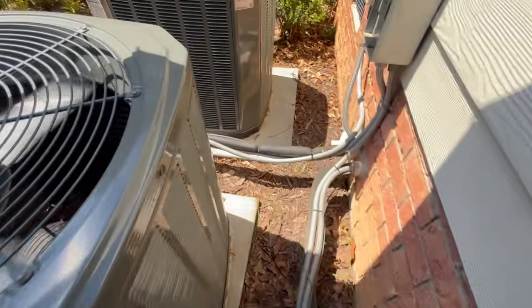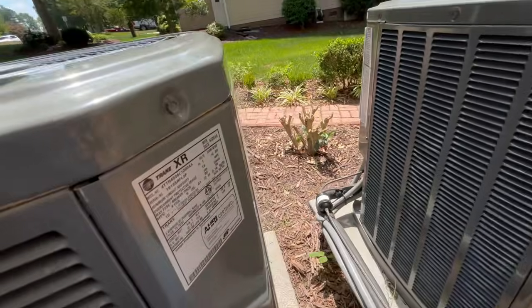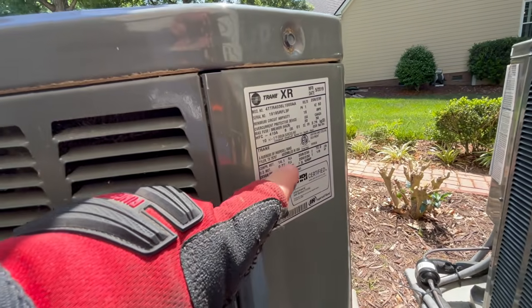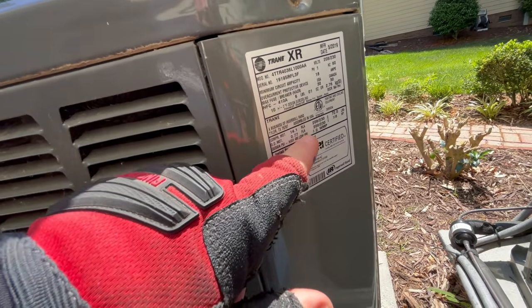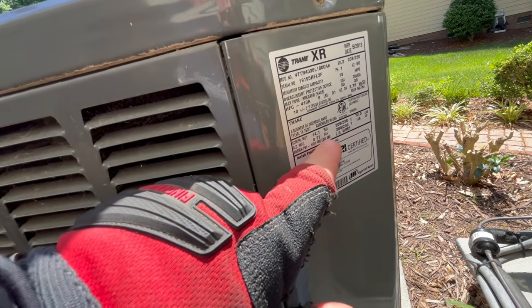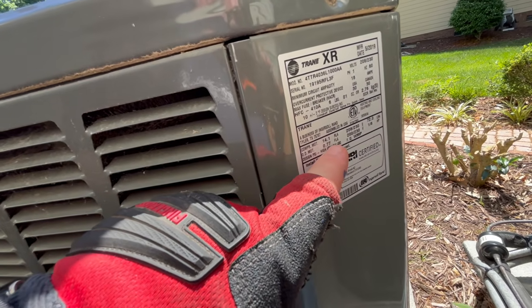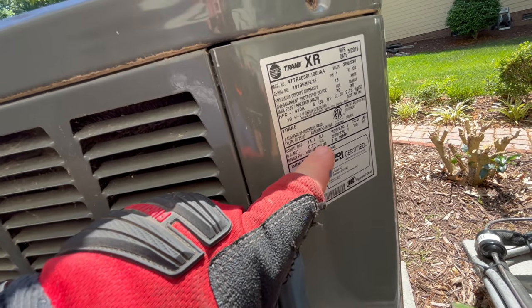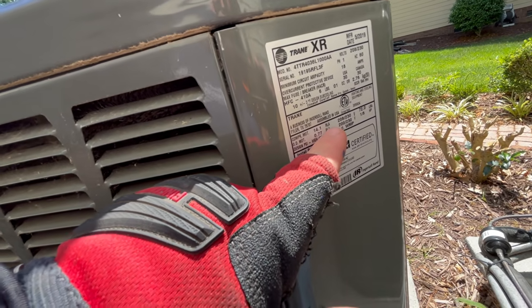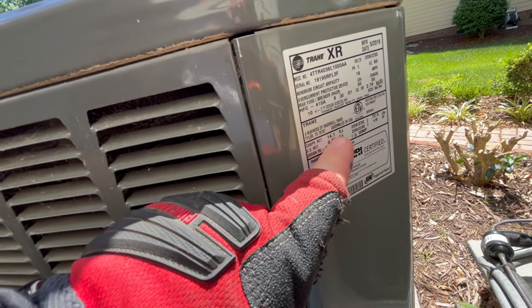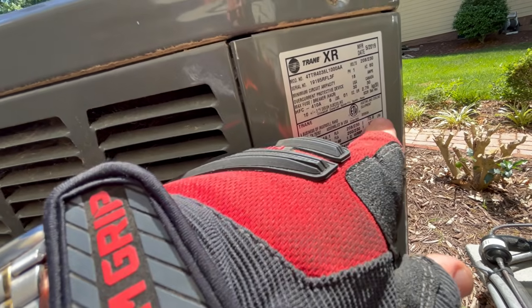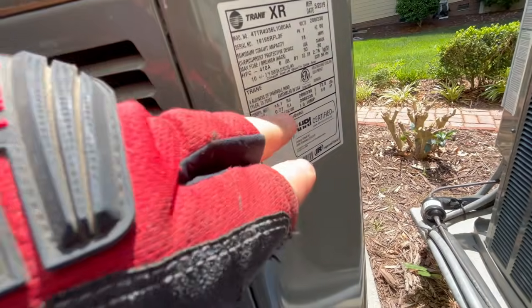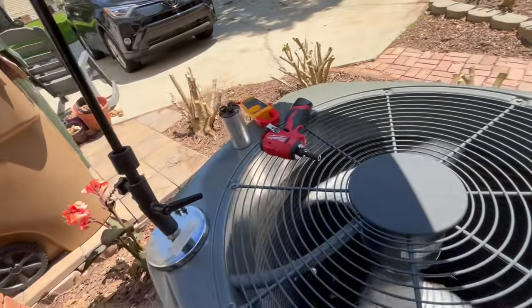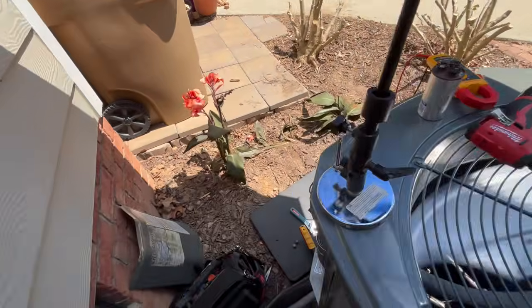Let's just see what our full load amps are on this system real quick. Outdoor motor, full load amps 0.77, we're at 0.67. And RLA on our compressor, running load amps, is 14, we're at 9.5. The LRA would be 72. So we're well under our RLA number. So I think everything's okay.